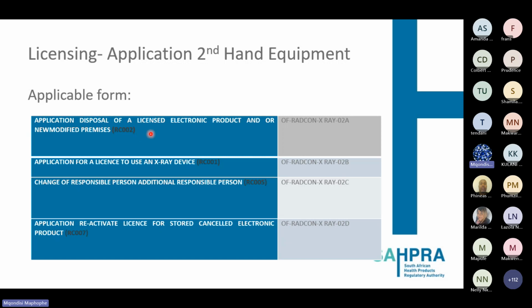By storing this machine, it means for that period we will not require annual QC for that machine. But as soon as you reactivate it, we will require what you call an acceptance test, because the machine has been in storage and is now back to clinical use.